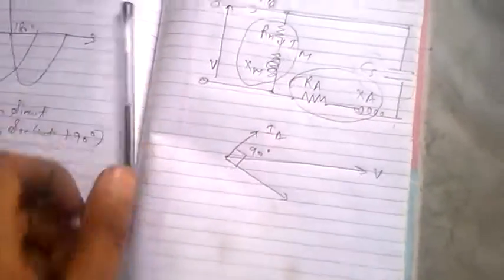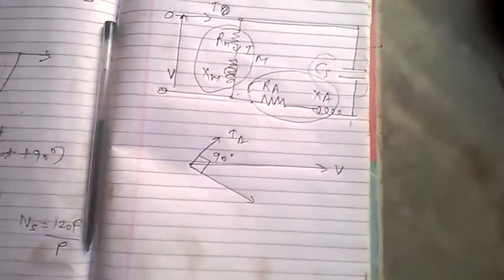That's called the phasor diagram of the circuit. By choosing a capacitor of the proper rating, the current Im in the main winding may be made to lag the current Ia in the auxiliary winding by 90 degrees. The single phase supply current is split into two phases to be applied to the stator windings.